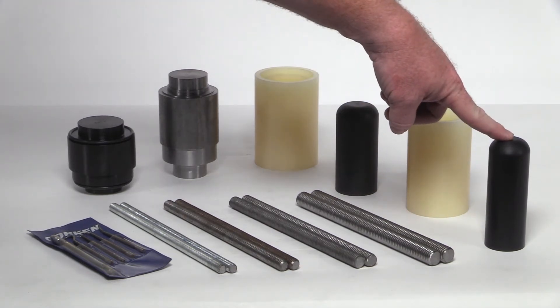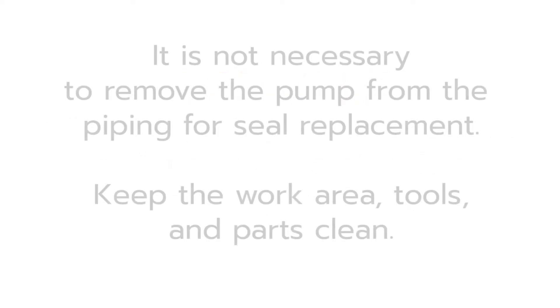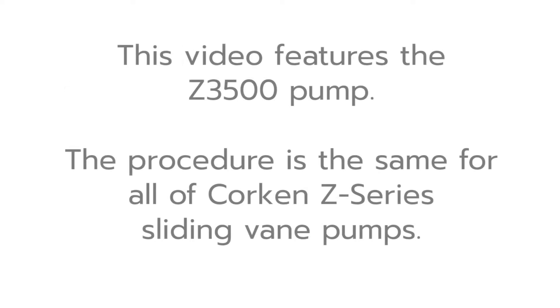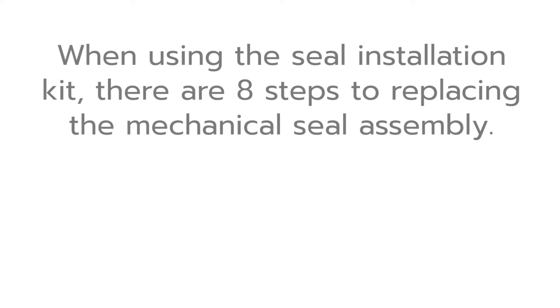Before performing any maintenance procedures, make sure the pump and system have been depressurized. The seal replacement is a simple procedure, so it is not necessary to remove the pump from the piping. Keep hands, work area, tools, and parts clean. This video features the Z3500 pump; however, the procedure is the same for all of Corken Z-Series sliding vane pumps. When using the seal installation kit, there are eight steps to replacing the mechanical seal assembly.